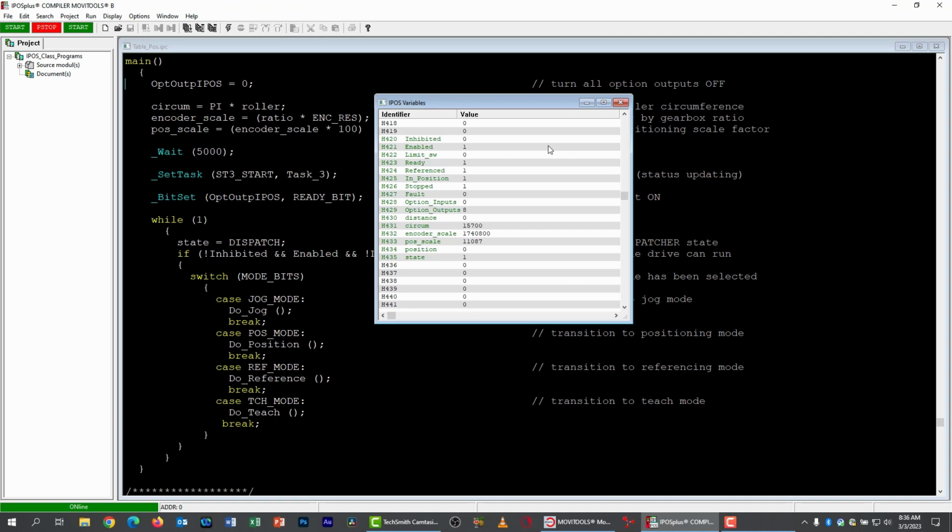That looks good. I can see that my motor stopped bit is 1. That means the motor isn't running, so my motor status light DO12 should be off, and I look at my control box and it is. That's good. Now let's go ahead and change a few states.